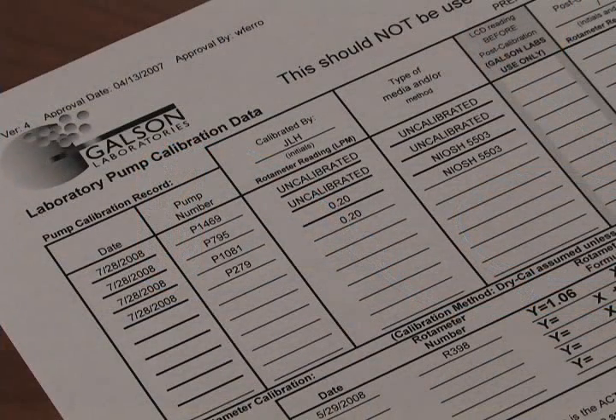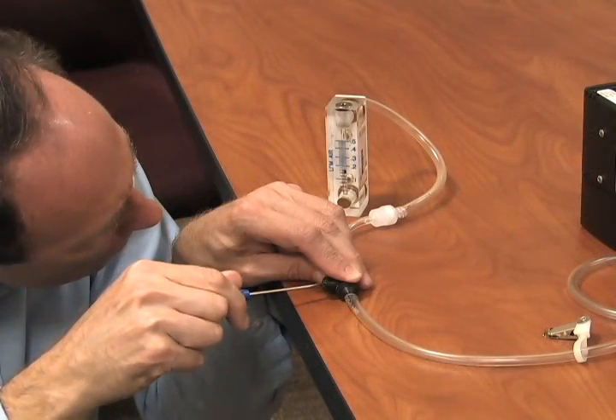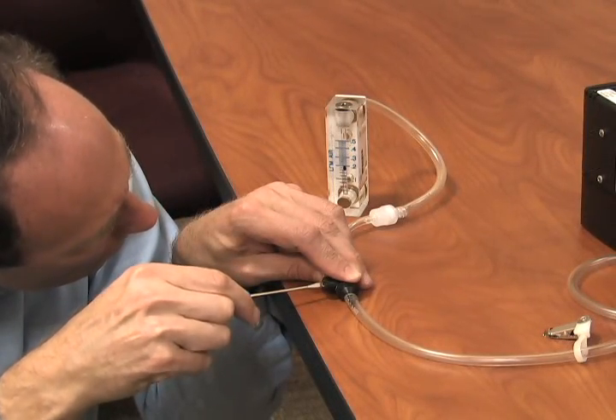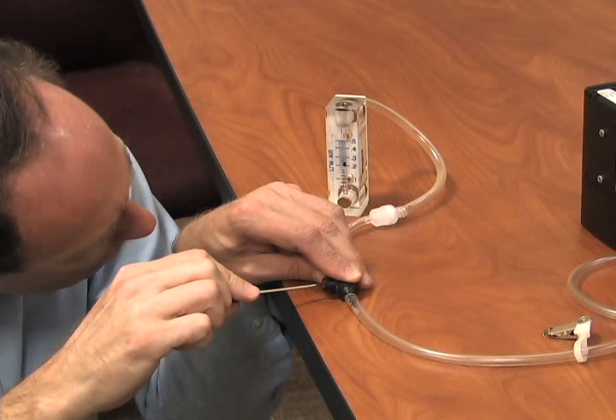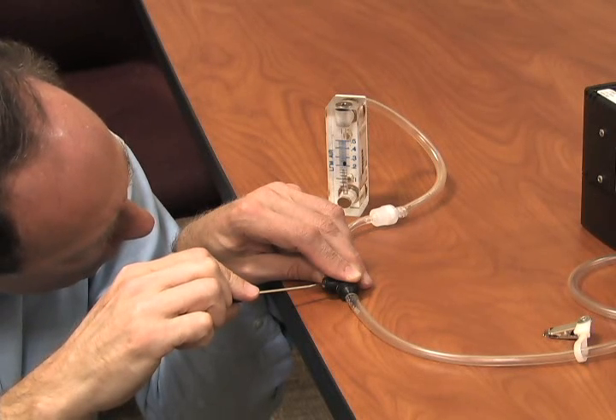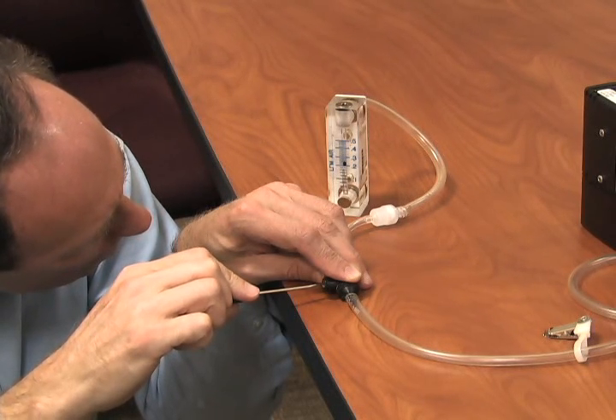All pumps have the lab calibration information on the field pump data sheets provided. The recommended pump flow rate is 0.20 liters per minute. With everything sitting on a level flat surface, check the ball float in the rotometer.